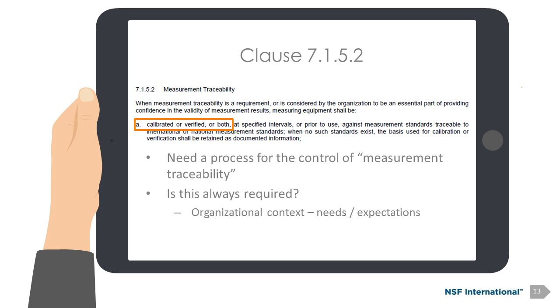Section 7.1.5.2, and I'm going to jump around a little bit, but I'll cover everything, I promise. 7.1.5.2 says when measurement traceability is a requirement or is considered by the organization to be an essential part of providing confidence in the validity of the results, the equipment needs to be calibrated or verified or both. We're going to talk about what calibrated versus verified means in a moment, but I wanted to highlight the first and more important thing here. We need a process. We need some methodology for controlling our measurement traceability activities.